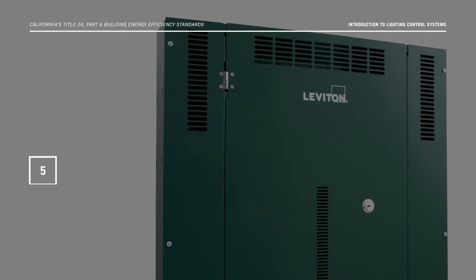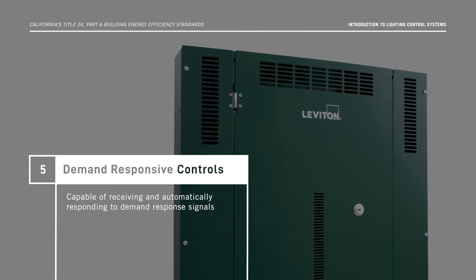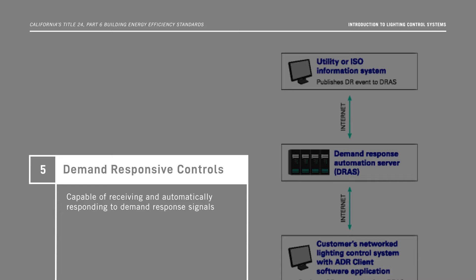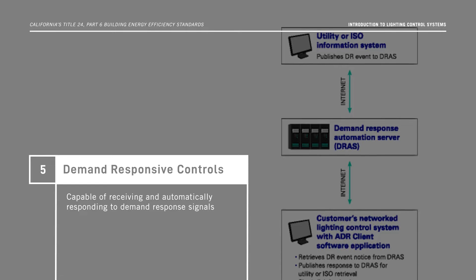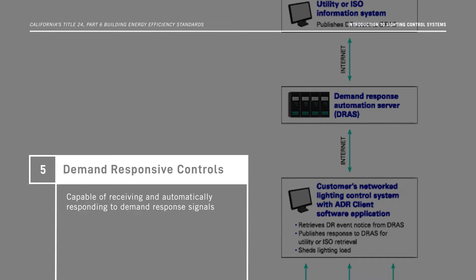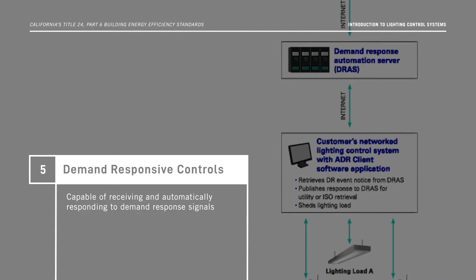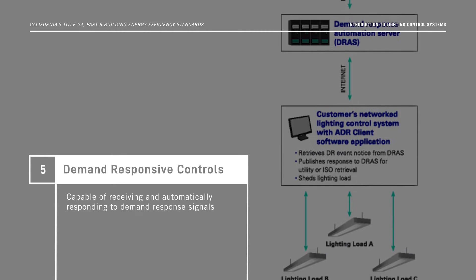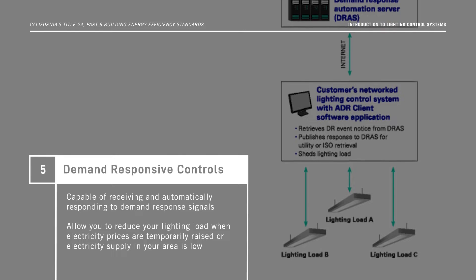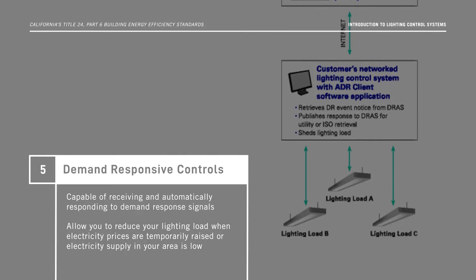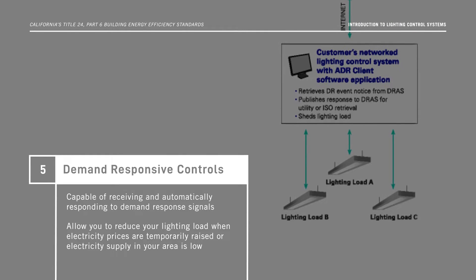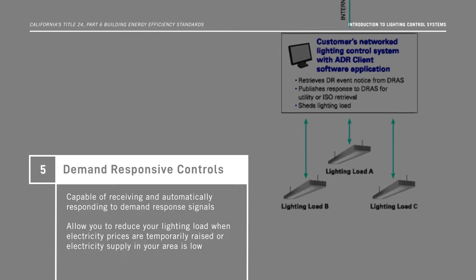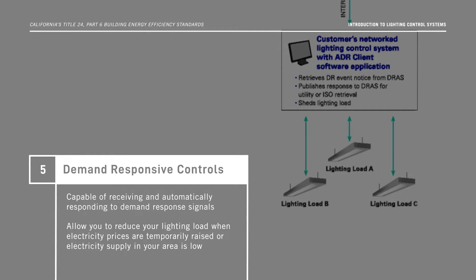The fifth and last control layer is demand responsive controls. These controls are capable of receiving and automatically responding to a demand-response signal sent from a utility or third-party program implementer. They allow you to reduce your lighting load when electricity prices are temporarily raised or the electricity supply in your area is critically low. These controls must meet requirements in Section 110.12 C, demand-responsive lighting controls.